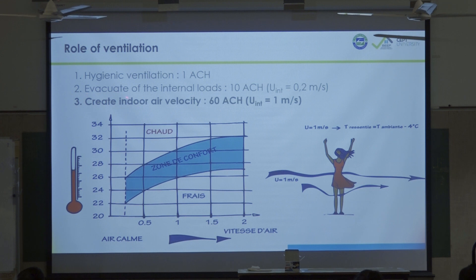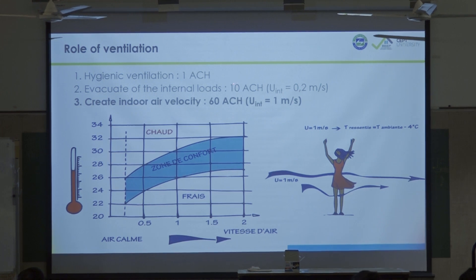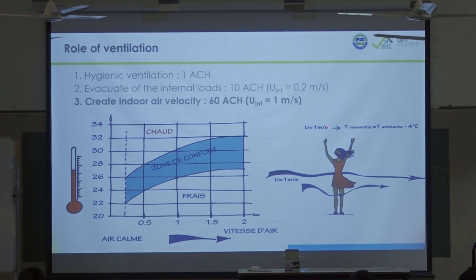If the wind potential is not enough on site, you will only be able to reach step two. As the air velocity is not enough, you have to add ceiling fans to generate an air velocity of one meter per second. If the wind potential is enough, then just thanks to the effect of the wind it will work on its own without ceiling fans.